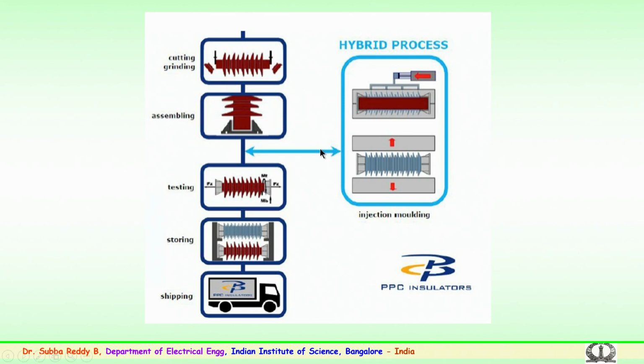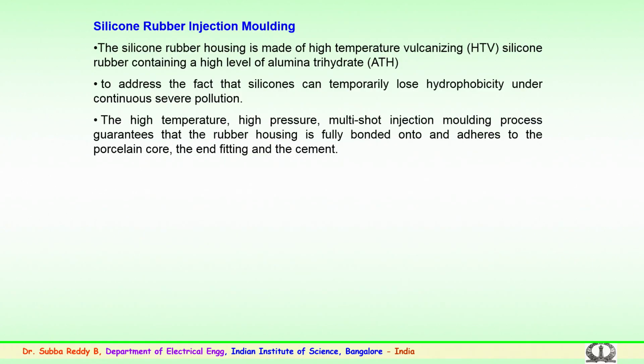So, after the testing, this is a process for both the hybrid as well as the porcelain technology, where it is being used for the hollow core or porcelain insulators. So, how is this done? Silicone rubber injection molding, which we have discussed during the manufacturing of the polymer insulators. Here the silicone rubber housing is made up of high temperature vulcanized silicone rubber containing a high level of aluminum trihydrate. ATH is the filler and silicone rubber, in the prescribed ratio of 50 and 50, plus some additive filler. This housing is made of high temperature vulcanized silicone rubber.